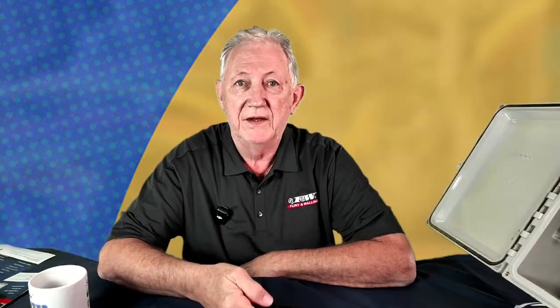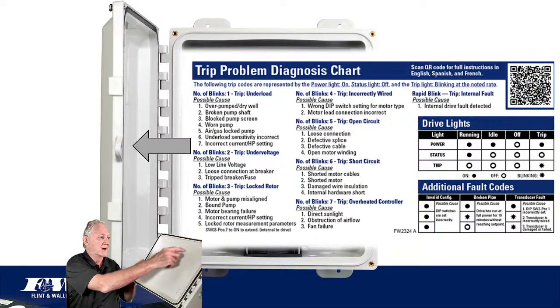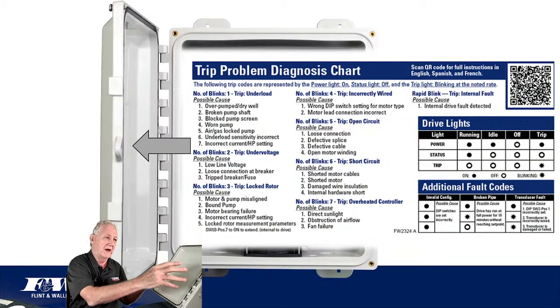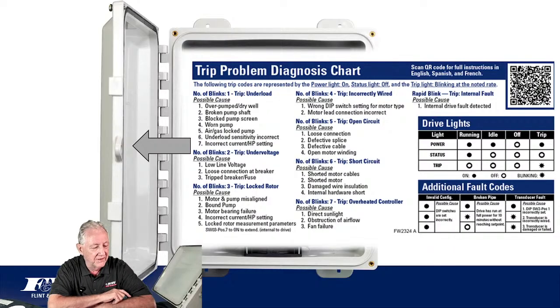So with that, I think we're going to go ahead and open up the inside of this enclosure, and at this point, Renee, I'm going to probably have to refer to a slide or two. So I'm going to go ahead and open this up. One of the things that you're going to see on the production drives, and I'm going to flip to this first slide here, is this label. This label will be affixed right inside this front cover. This label is going to indicate those lights that we talked about up front, particularly the status and the trip lights, because those two lights can either be solid or blinking.